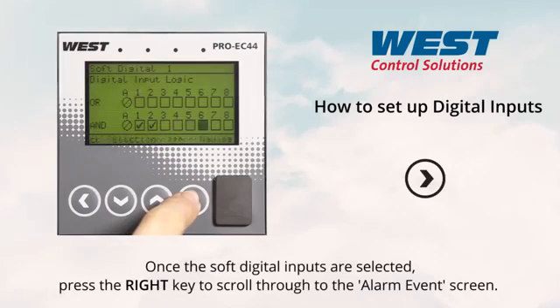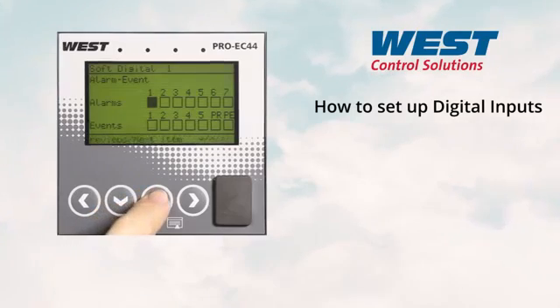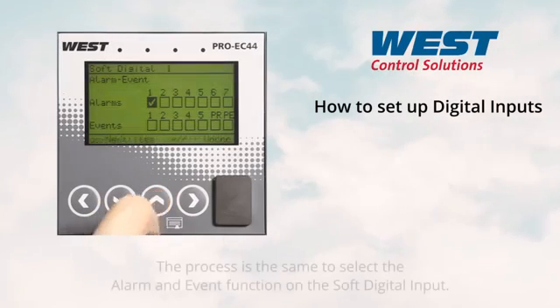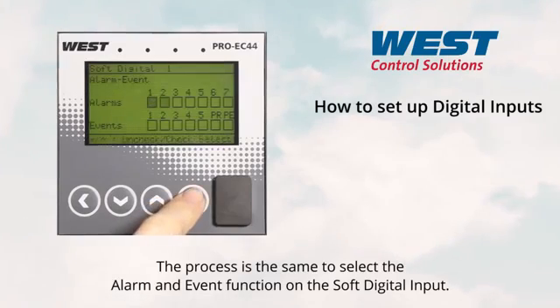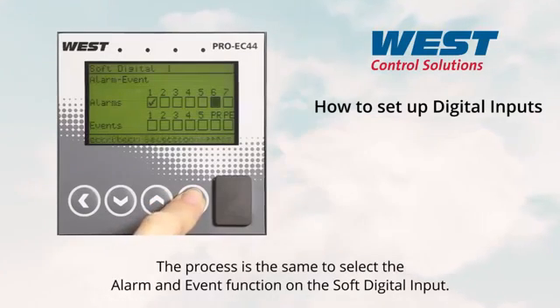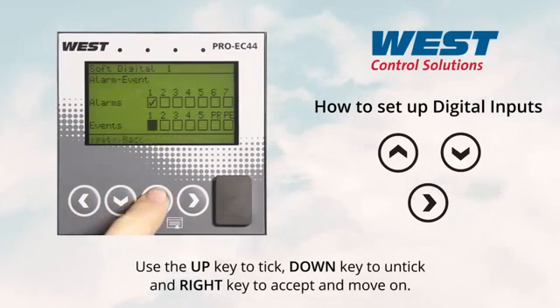Once the soft digital inputs are selected, press the right key to scroll through to the alarm event screen. The process is the same to select the alarm and event function on the soft digital inputs — use the up key to tick, down key to untick, and the right key to accept and move on.